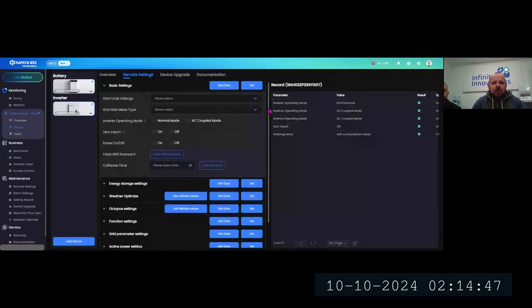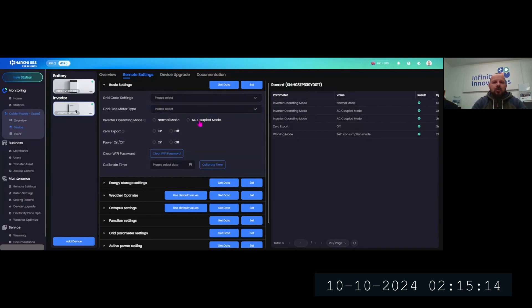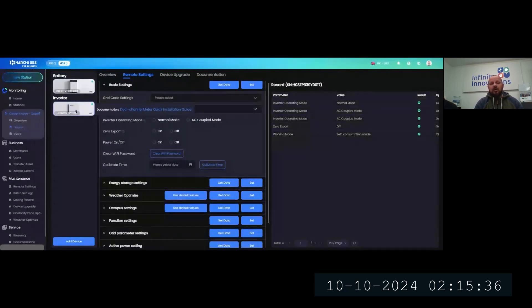For those wanting to install AC coupled inverters using a hybrid model with Hanshu, this unit can physically do that. If you're going to a property that already has a solar installation and you want to fit an inverter to store that energy, usually you'd install an AC inverter. The Hanshu hybrids have that ability — you go into AC couple mode, install a dual-channel meter that monitors both the grid and the solar, and the system knows of any excess energy. It will steal that energy and store it in the hybrid inverter's batteries, using it when load increases and demands extra power.